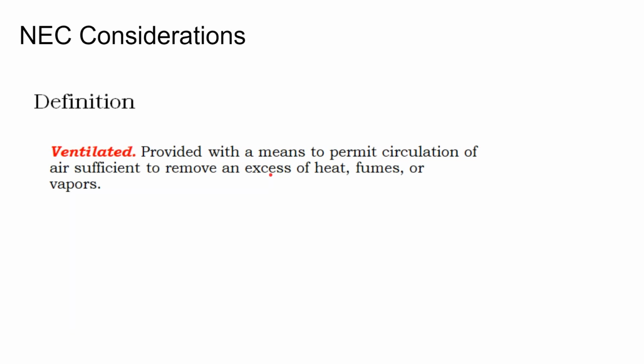But there are ventilation requirements that are intended to prevent the hydrogen gas from accumulating anywhere in the building. Now, what that means is the ventilation and air conditioning. If you have your batteries in an air conditioned room, that will be fire code compliant because you have an air handling system, but you have to make sure you're actually using the air conditioner. So if you're not using the air conditioner in the spring or in the fall, you still need to be blowing that fan through the room and circulating the air.